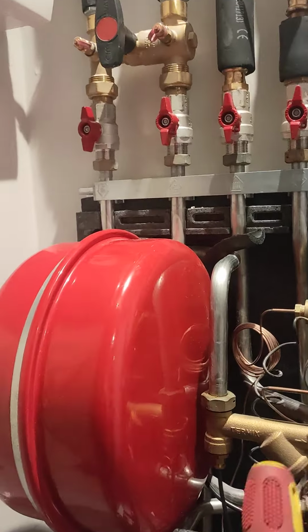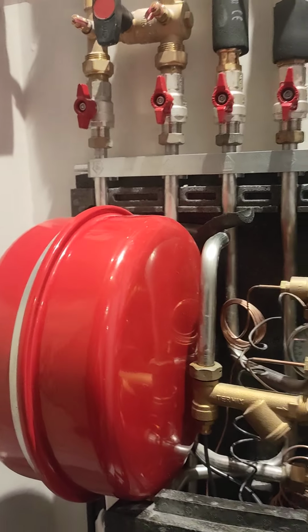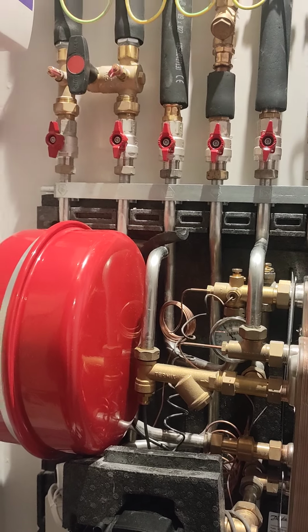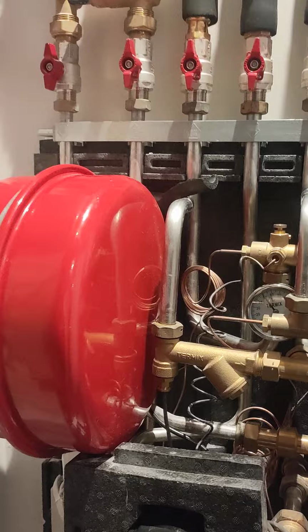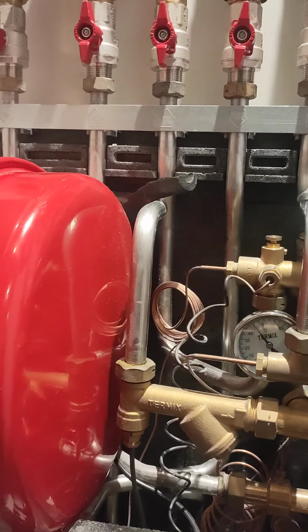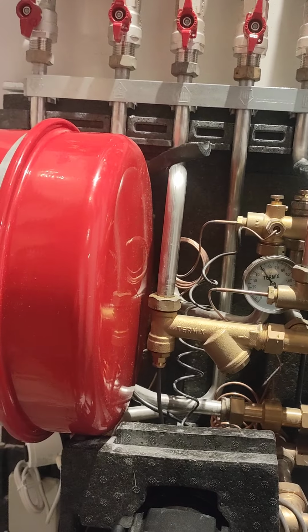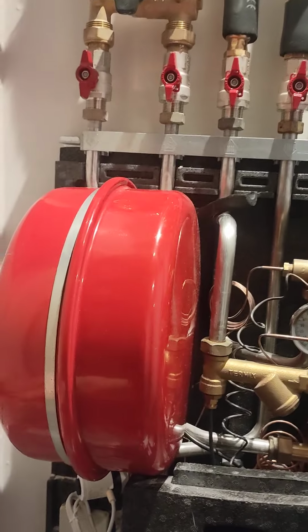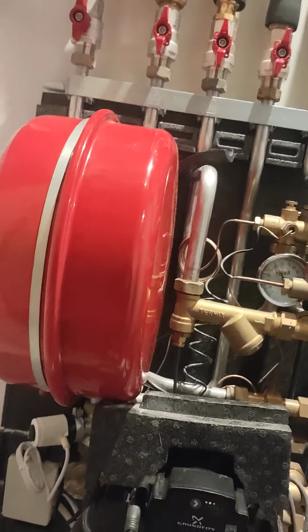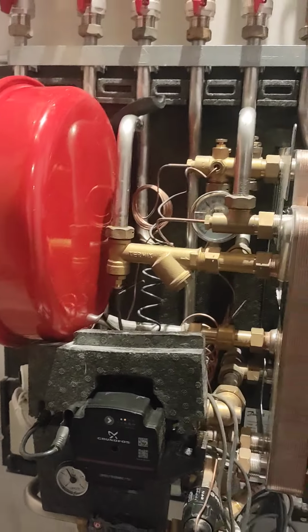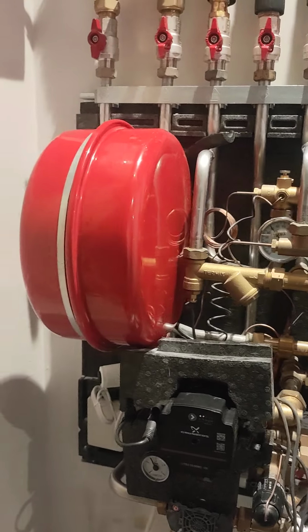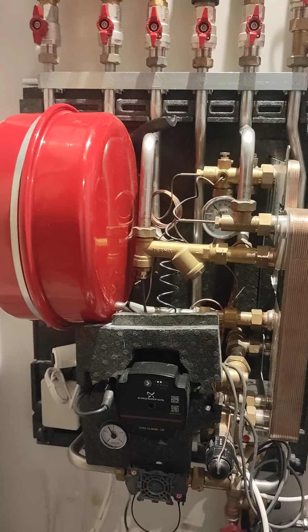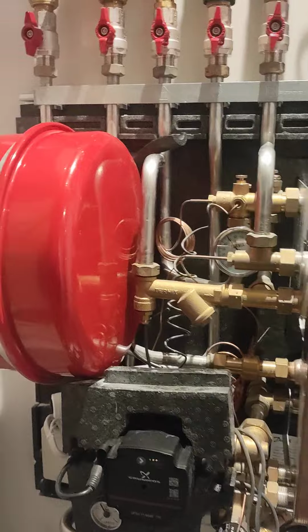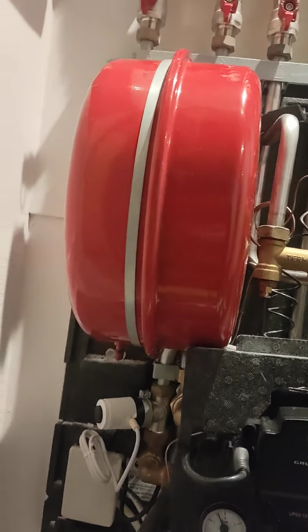Also, make sure you bang the expansion vessel to check if it's still full of air. It should be holding at 1 bar. It's quite a good vessel, looks like they may have replaced it already at some point.